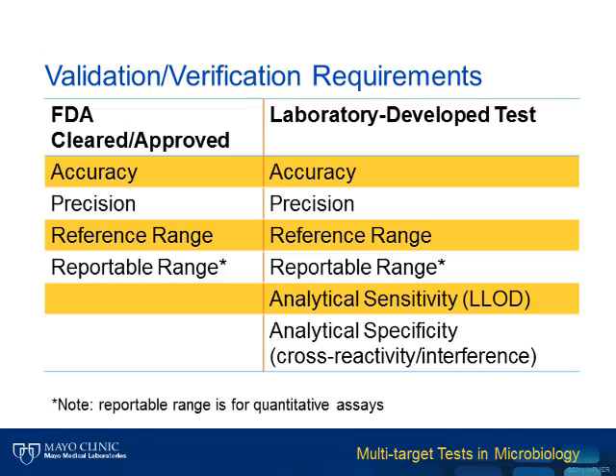The Clinical Laboratory Improvement Act, or CLIA, provides requirements that laboratories must follow when characterizing the performance of their tests. More work is required for laboratory-developed tests. FDA-cleared and approved tests must be characterized in terms of accuracy — which includes sensitivity and specificity — precision, reference range, and reportable range. Laboratory-developed tests, in addition, need to be evaluated for analytical sensitivity or lower limit of detection, as well as analytical specificity, which includes cross-reactivity with other targets and interferences from specimen components. Note that the reportable range applies to quantitative assays only.